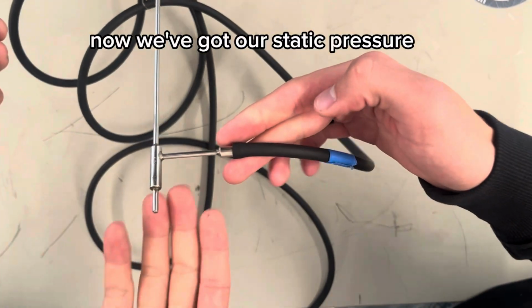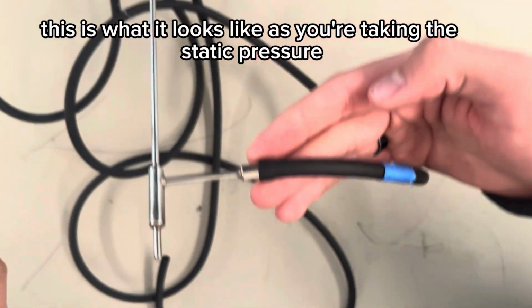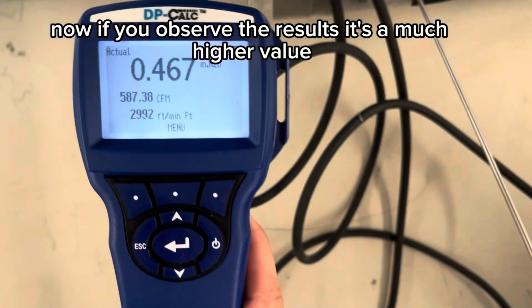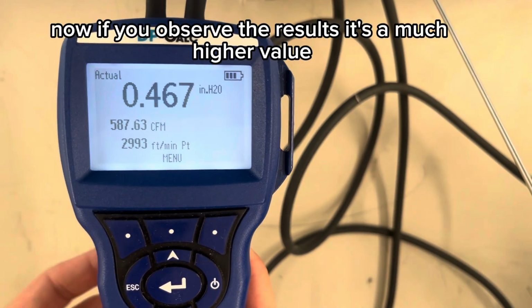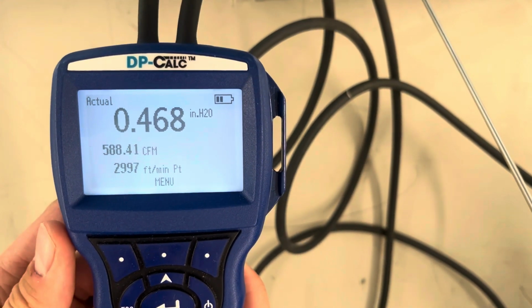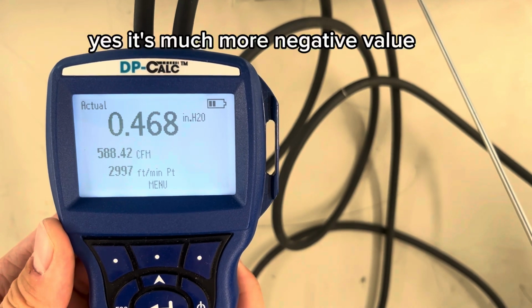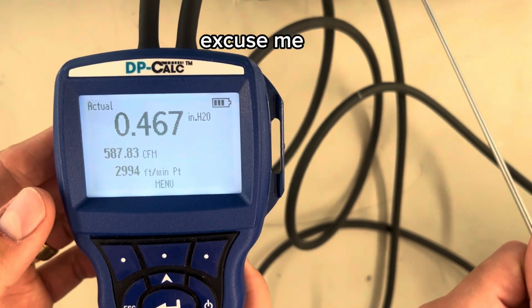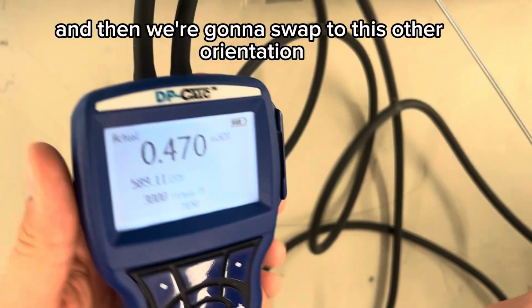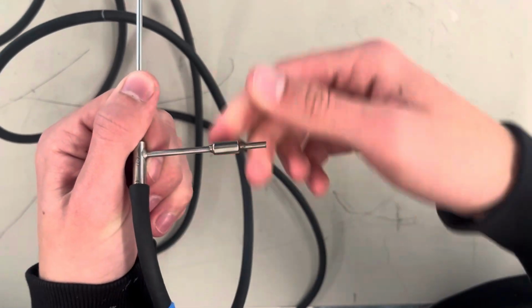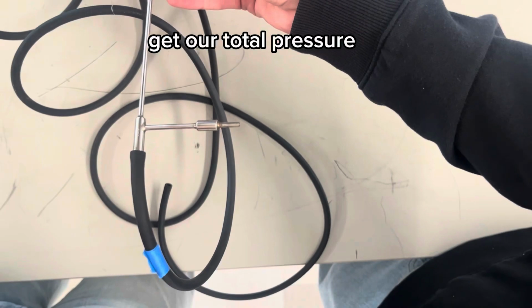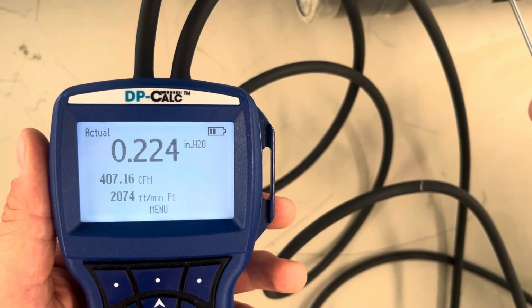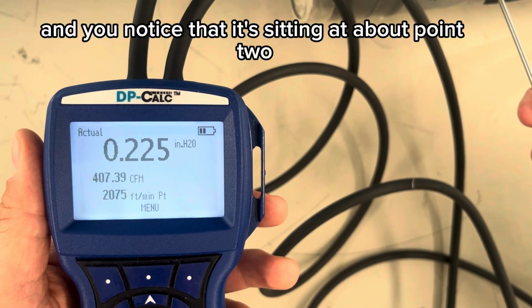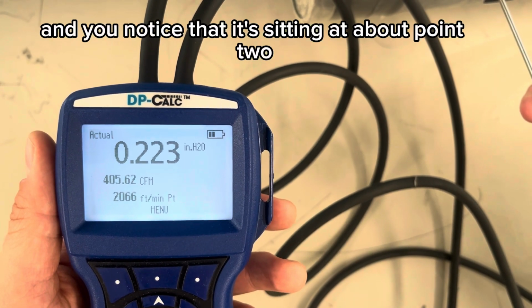Static. Now we've got our static pressure. This is what it looks like as you're taking the static pressure. If you observe the results, it's a much higher value. See, negative. Yes, it's a much more negative value, excuse me. And then we're going to swap to this other orientation to get our total pressure. And you notice that it's sitting at about 0.2.